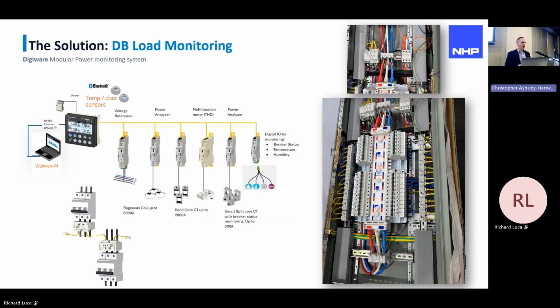And that's what it looks like from a component level. Inside a DB on the right, you can see the modules, and we can have various CT connections on the individual loads. The beauty about this system is the accuracy class is maintained at class 0.5 throughout the entire network. With traditional wiring, when a contractor goes to wire your system, the spec may call for a class 0.2 meter. By the time the contractor wires it, the whole system's probably a class 1. So you've got to be careful in how you install this system. But this system here is maintained at 0.5 accuracy.